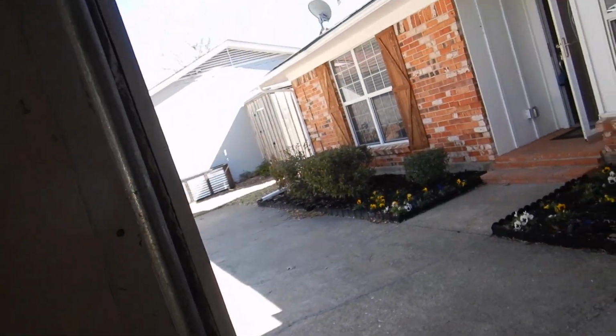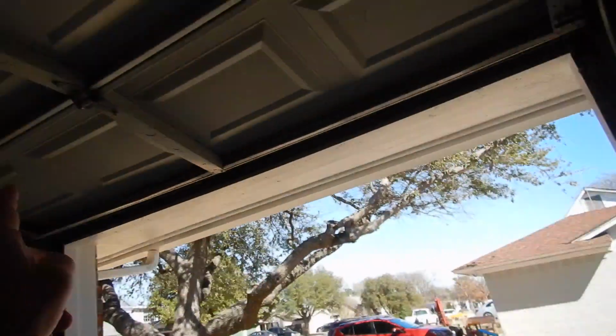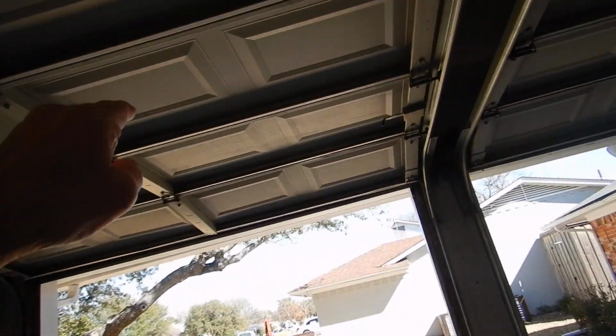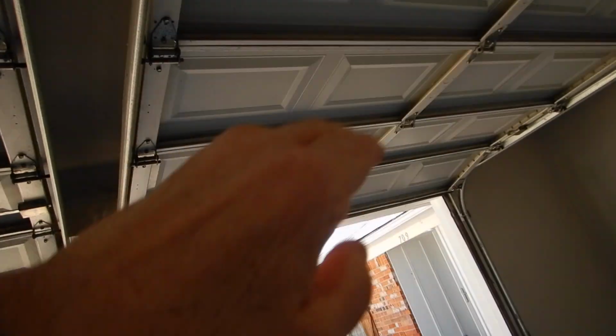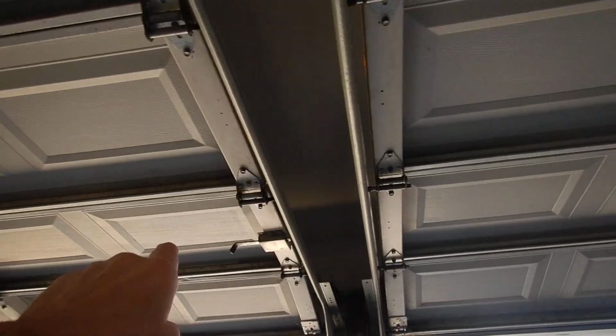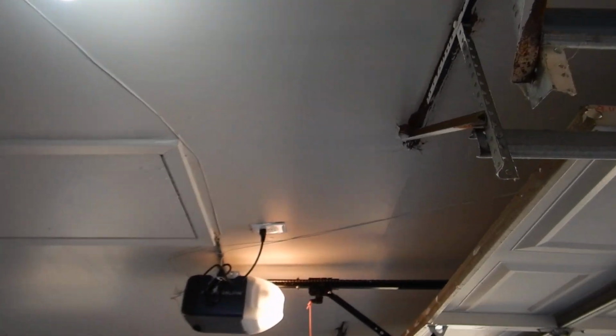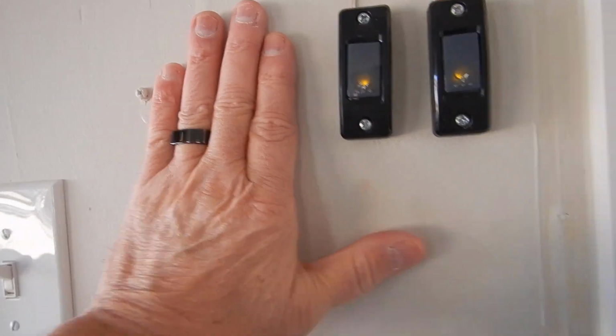Oh, no, not the wrong kind of staples. We do not have pinch notices on the corners of the doors. We do not have a safety notice posted inside the doors. We do not have safety door handles installed inside of the doors. Our door locks are not decommissioned. We do not have GFCI protection on the electric power going to the doors. Our control buttons are too close to the door threshold and the garage floor, and we do not have a safety notice posted on them either.